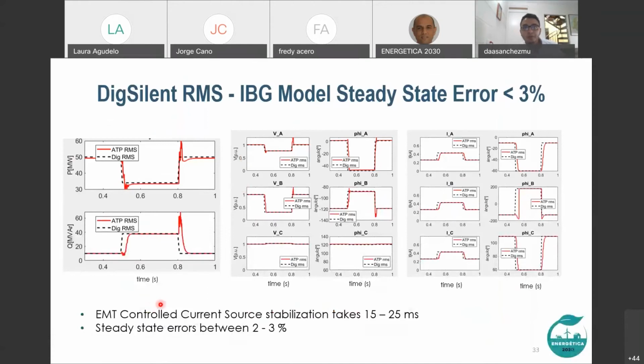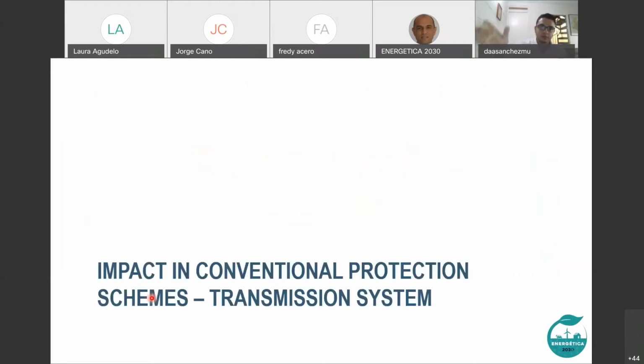We also find that the EMT model takes between 15 and 25 milliseconds for transient stabilization. This migration was successful and has allowed us to analyze the effect of IBG, inverter-based generation, in more cases and more scenarios, remembering always that DIgSILENT is the most popular power system simulation tool here in Colombia. So that's all of inverter-based generation modeling, all the steps that we have made.